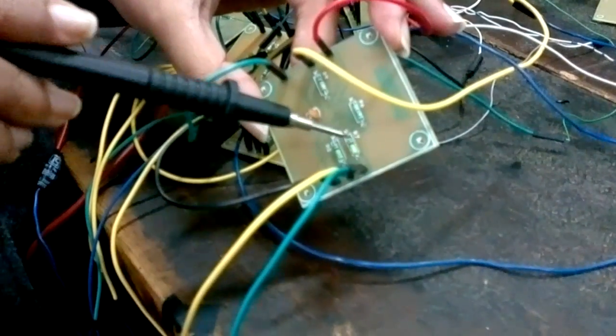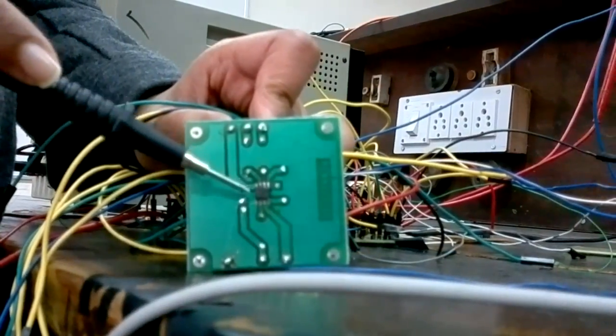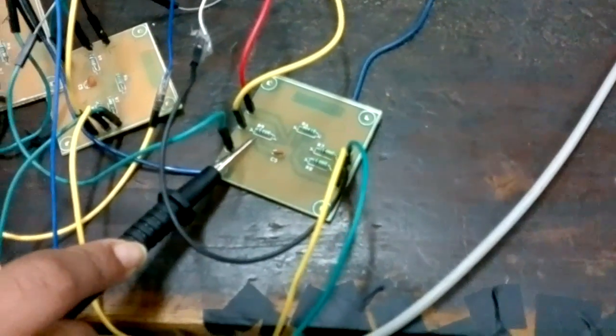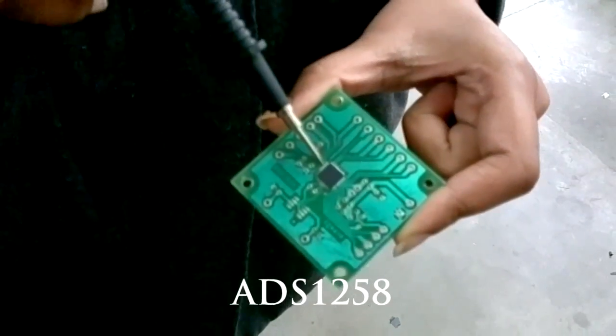As the signal coming from the electrodes is very weak, INA121 has been used to enhance the signal. 100 kΩ resistors are used before the differential input of INA121 for safety purposes. Instrumentation gain has been set to 4 using a 15.5 kΩ resistor. The outputs of the 3 instrumentation amplifiers are multiplexed using a sigma delta analog to digital converter ADS1258.